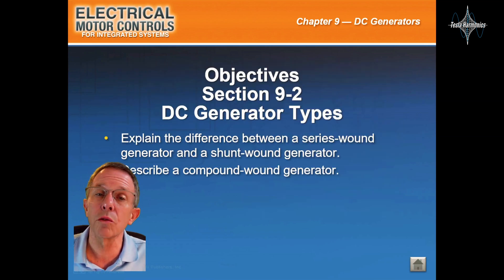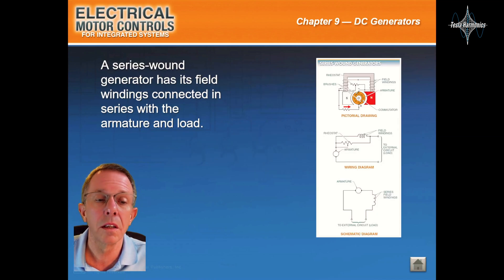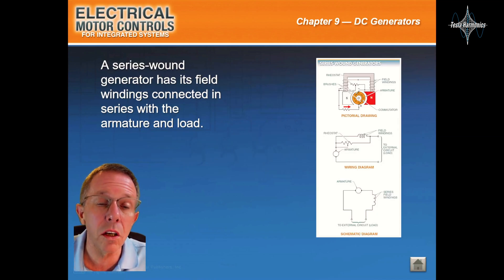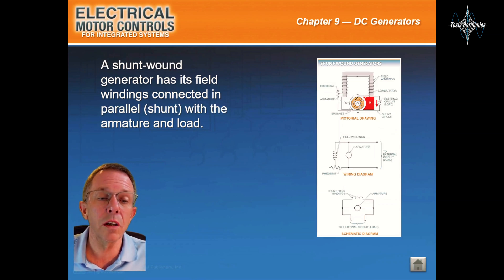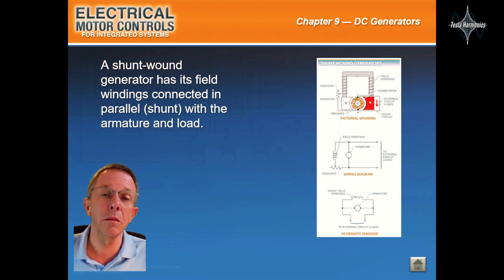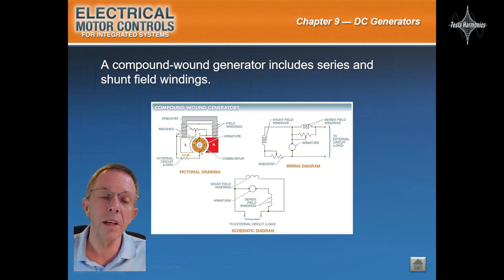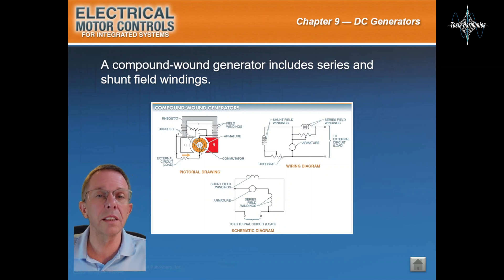Section 9.2, DC generator types. A series-wound generator has its field windings connected in series with the armature and the load. A shunt-wound generator has its field windings connected in parallel, or shunt, with the armature and load. A compound-wound generator includes series and shunt field windings.